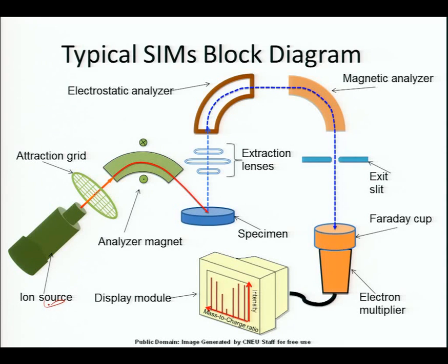So basically what we do to get these counts, on these individual masses, is we'll adjust the magnetic field so we select the appropriate ion. When we select that appropriate ion, we filter that ion out that has the appropriate charge to mass ratio that can make it around the bend. Then we'll sit there for a few seconds or whatever the timing on the machine is, and we'll do a count at that point.